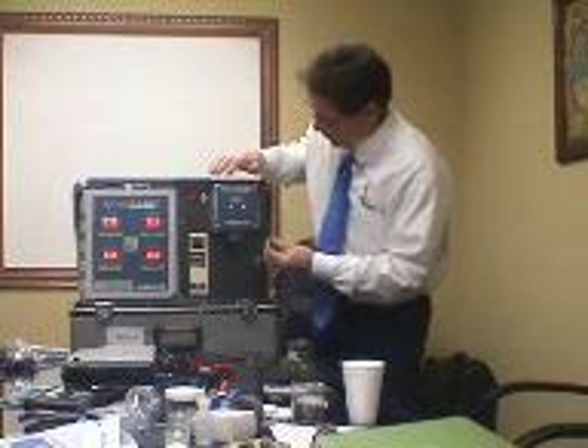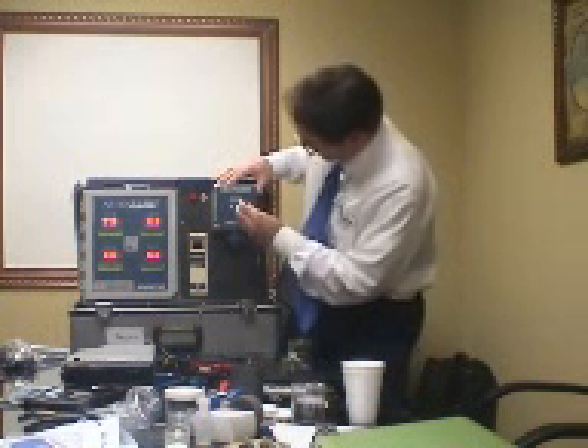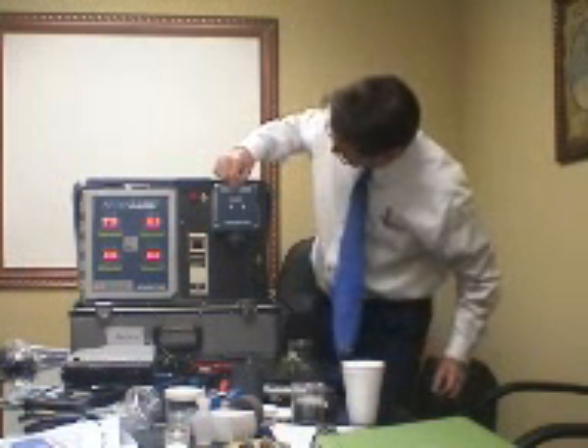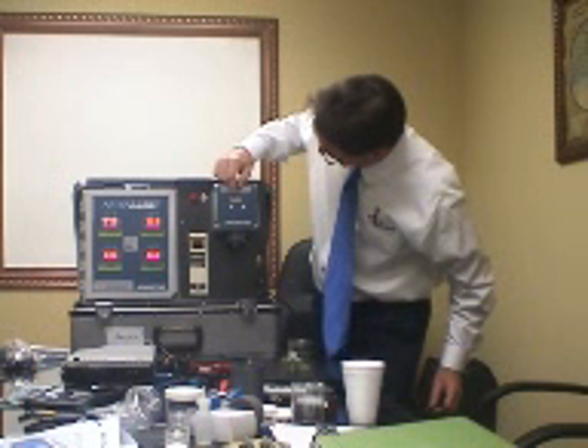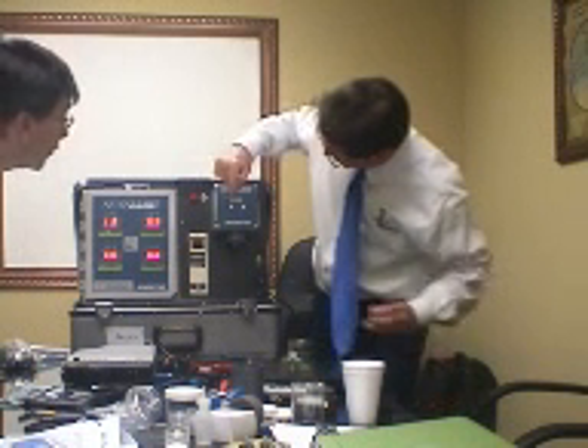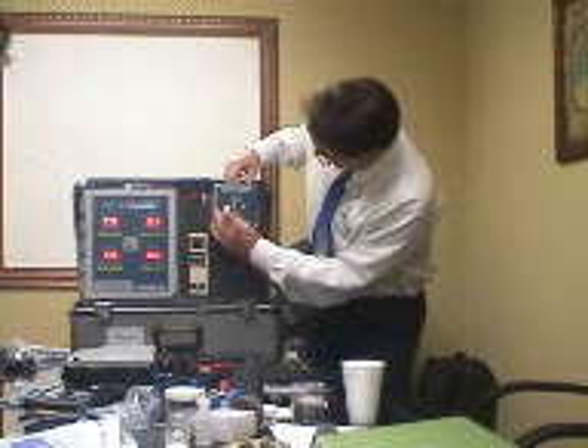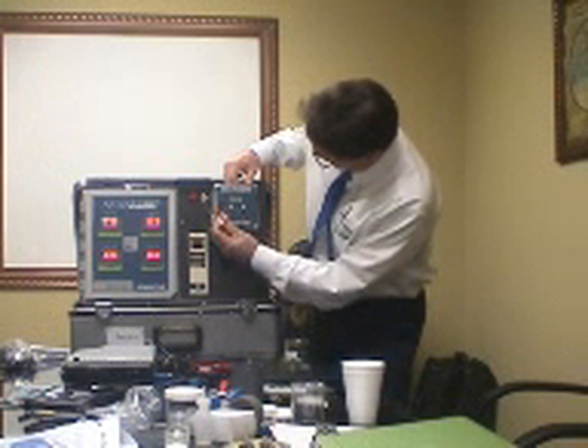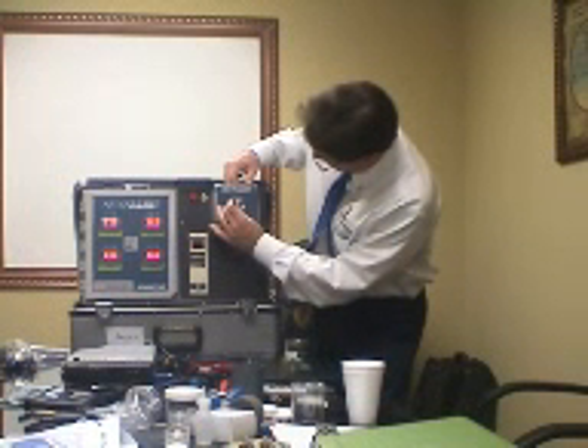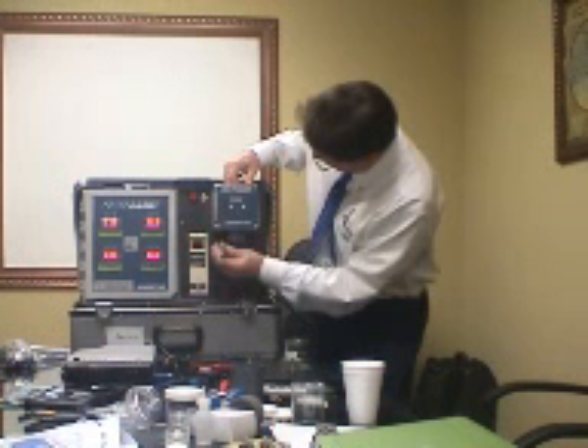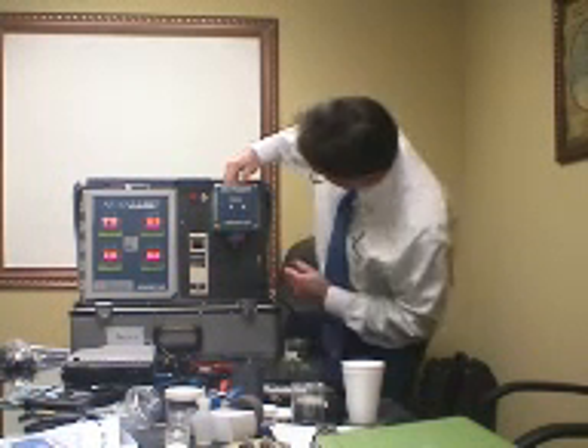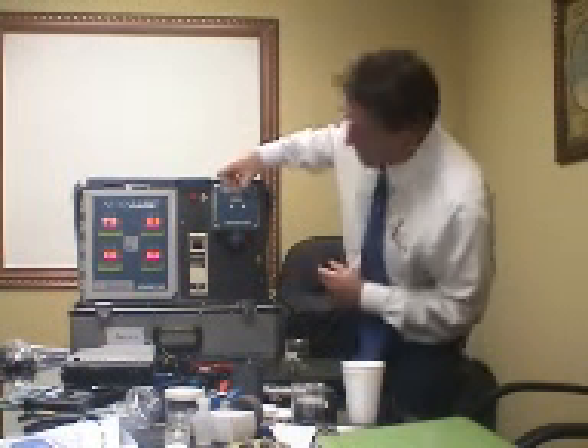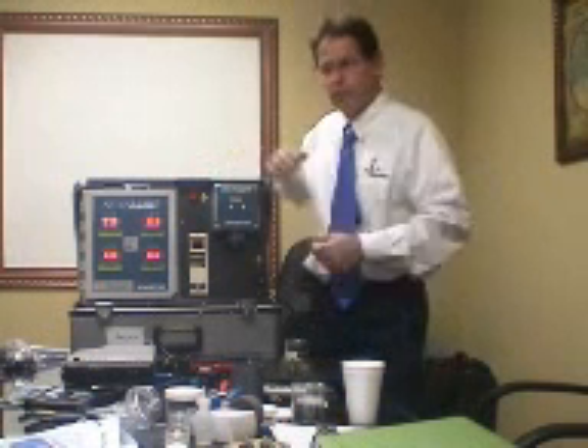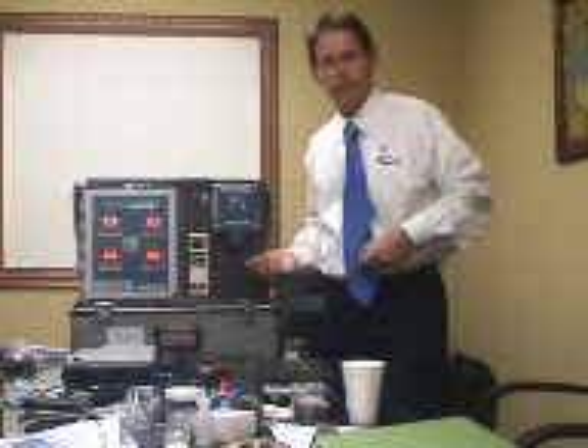To calibrate one of these units, you simply touch the span button, and it says enter concentration, up or down. It says 21.4, so this is the up button. So we're going to make up 21.5, 21.6, 21.7, 21.8, 21.9, 21.9% by volume. I've told it we're preparing to apply 21.9% gas.